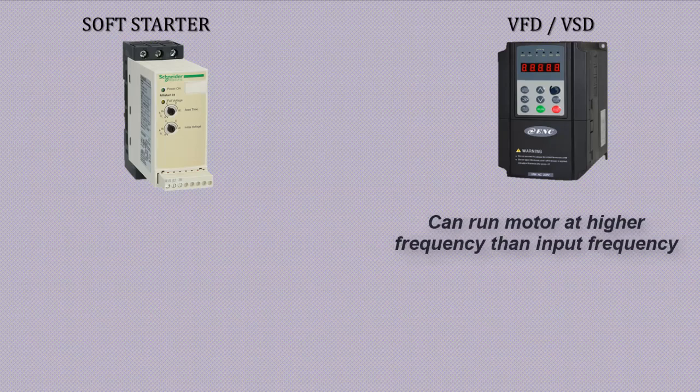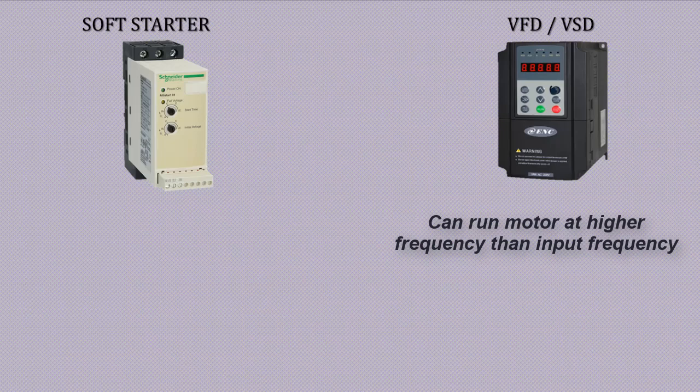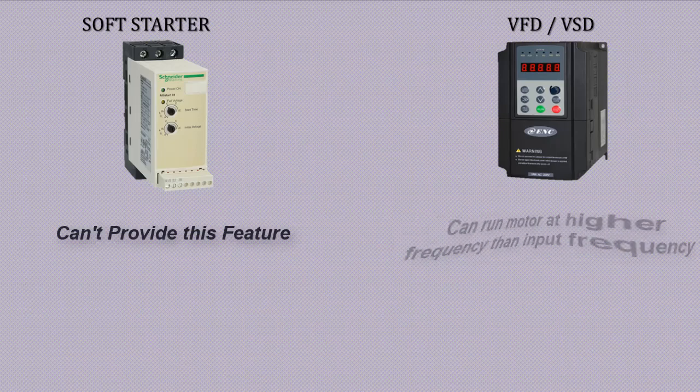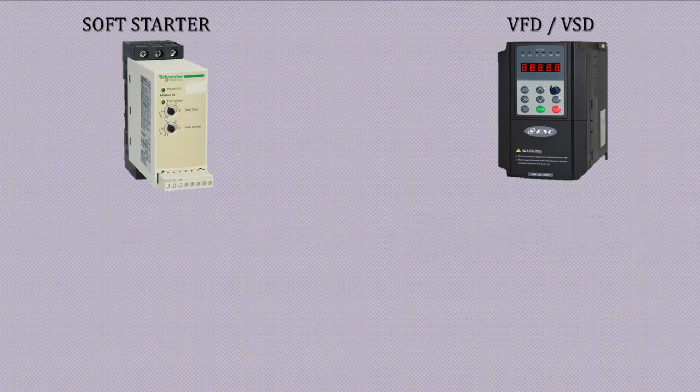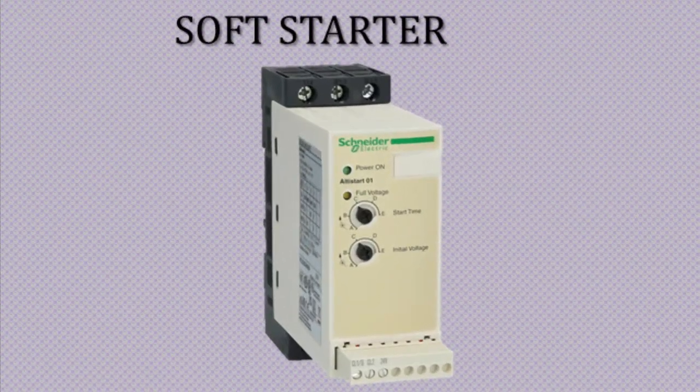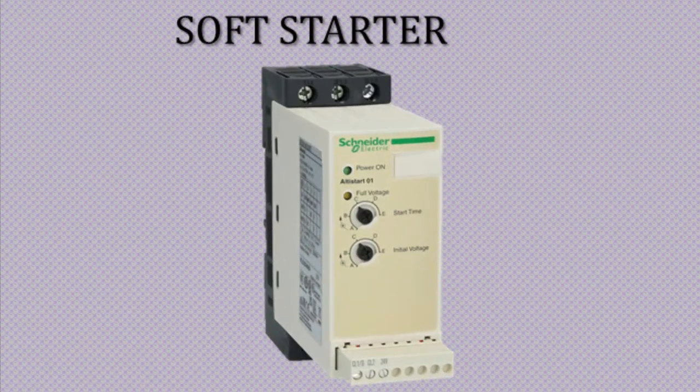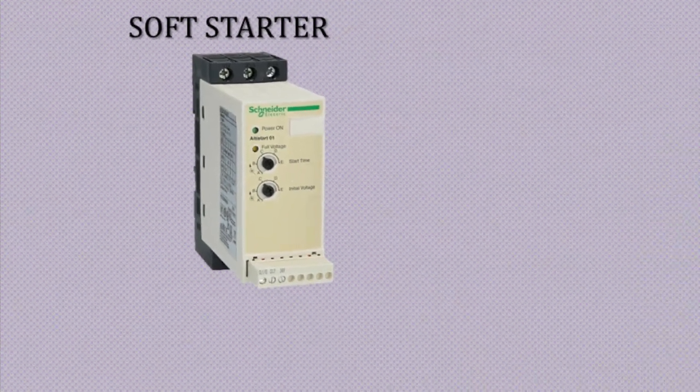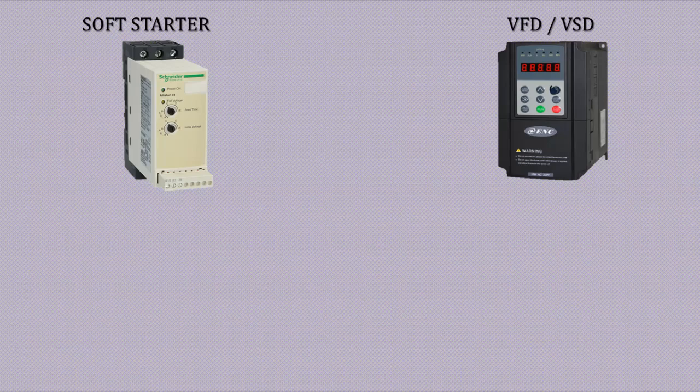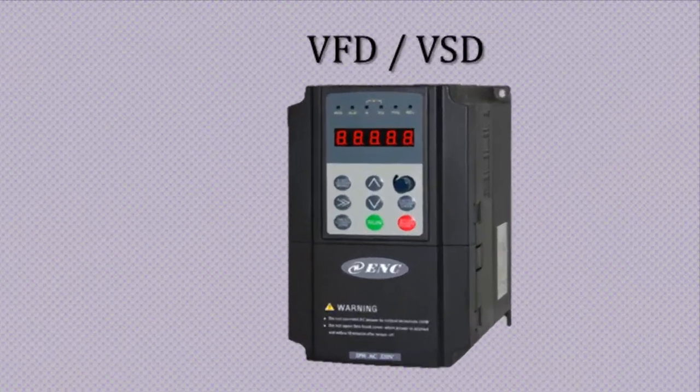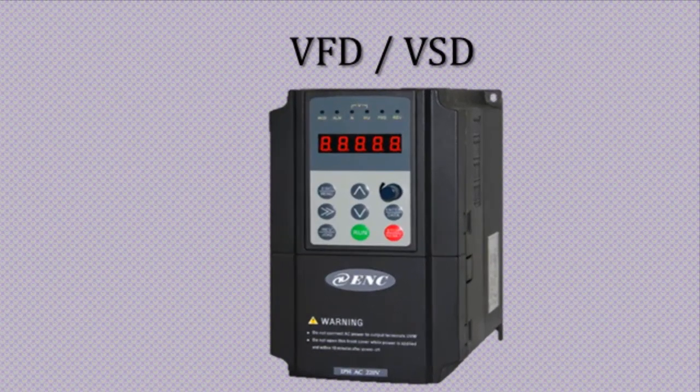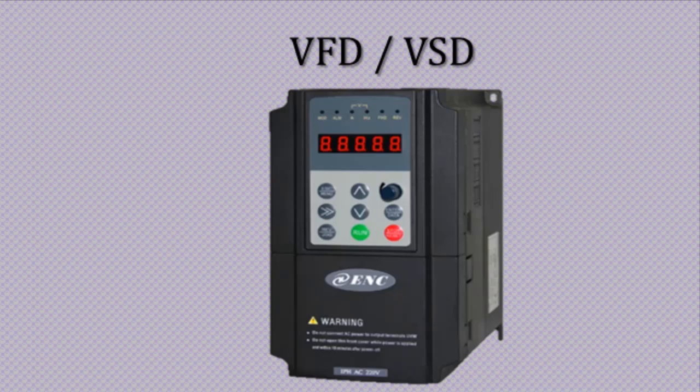The conclusion is if you want only to limit inrush current and there is no requirement of speed and torque control then select soft starter. But if you want to control torque and speed of motor or to run motor other than its rated speed or motor rated frequency is higher than utility supply frequency then choose variable frequency drive. Soft starter can't work for these purposes.